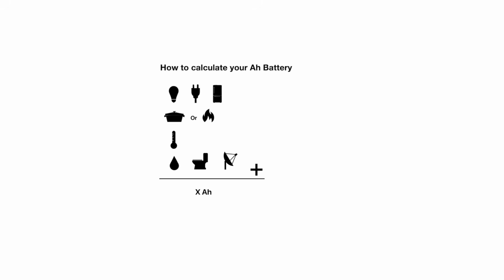Now here's the key step. We've added up the power usage of all our devices. Think of it like budgeting: if you don't know what you're spending, you don't know how much you need. That's how we landed around 120 amp hours a day. Times our requirement to spend a minimum of 3 days off-grid, that's 360 amp hours. Plus 10% is about 400 amp hours, which then directly determines your battery size.